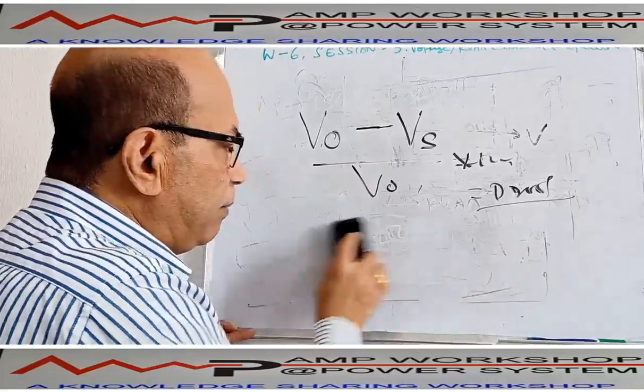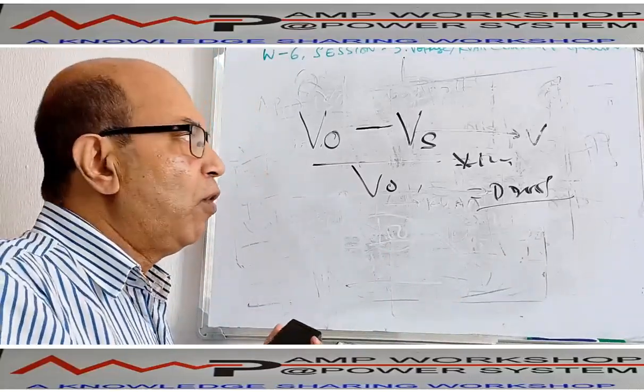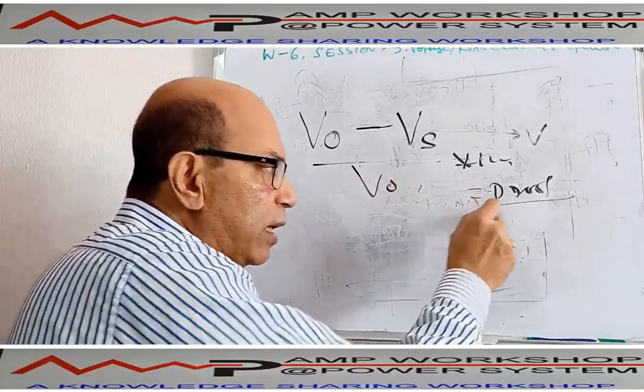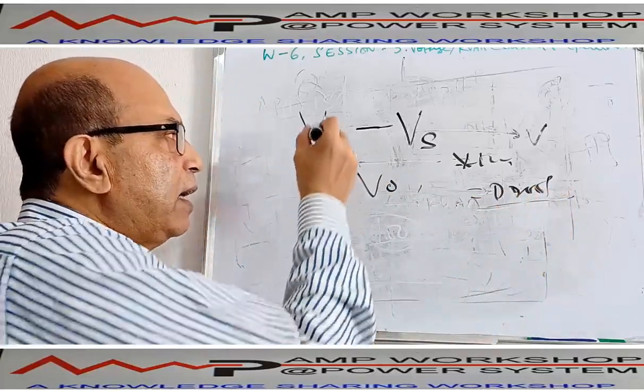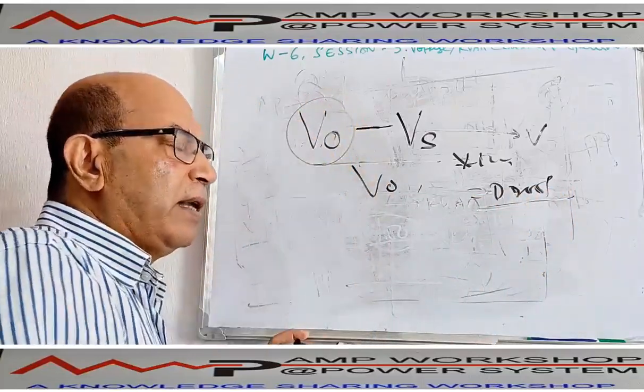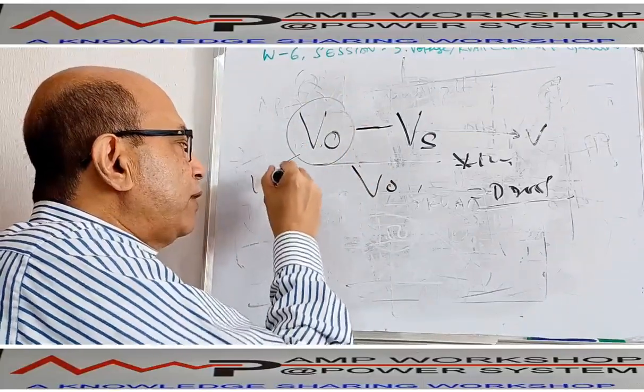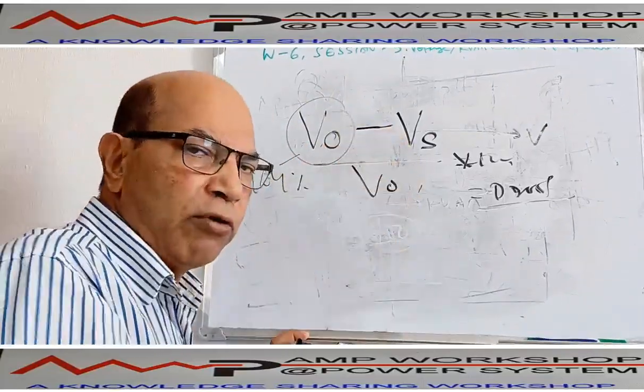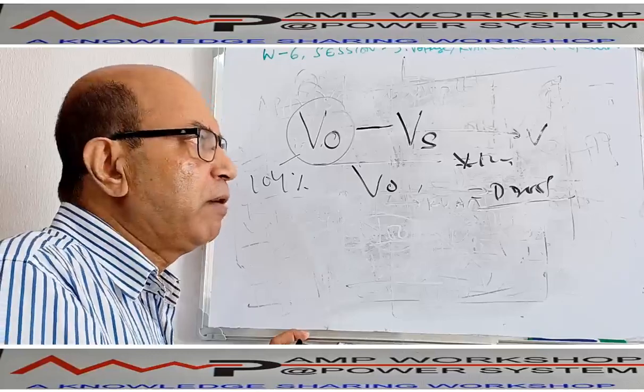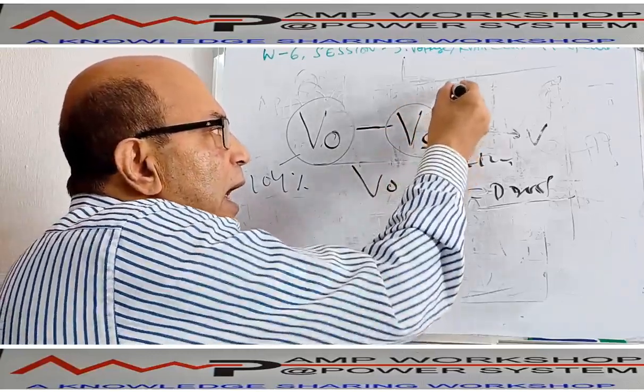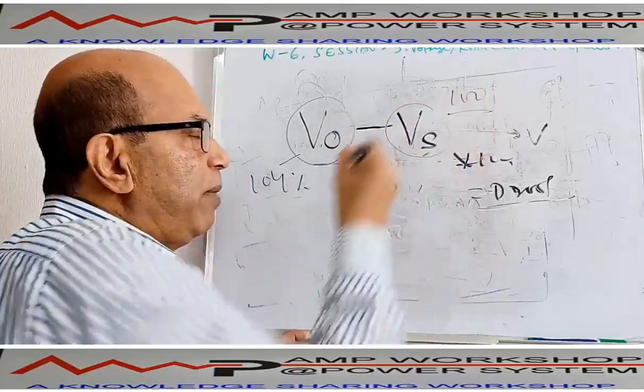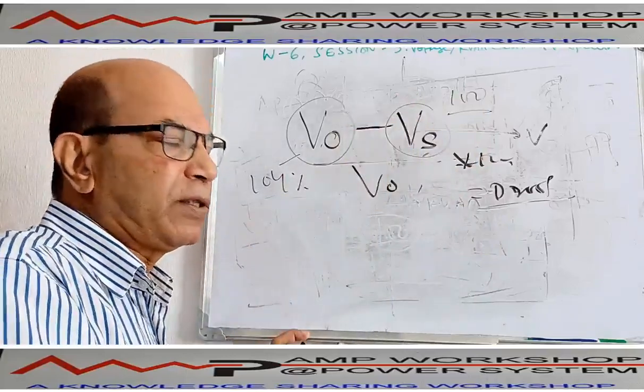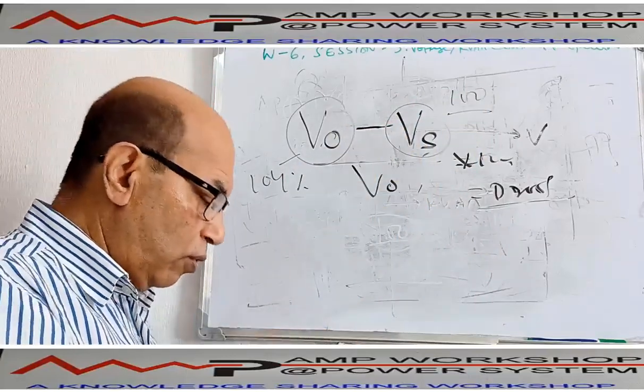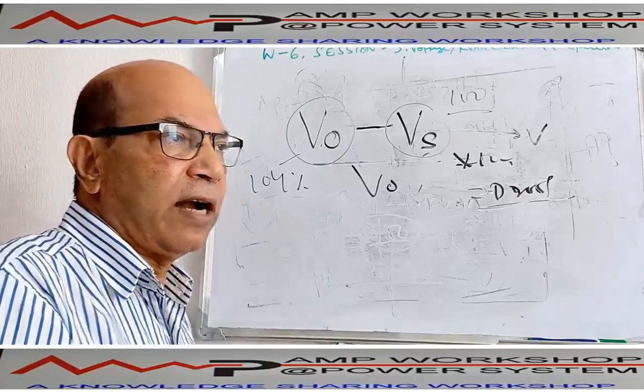And the meaning of this 4% droop is that when the machine is not drawing any kVAr, the voltage V0 will be 104%. And when the machine is fully loaded with reactive power, the voltage VS will be 100%. So this difference will be 4%. That is the droop. So with this droop characteristic, what is the advantage?